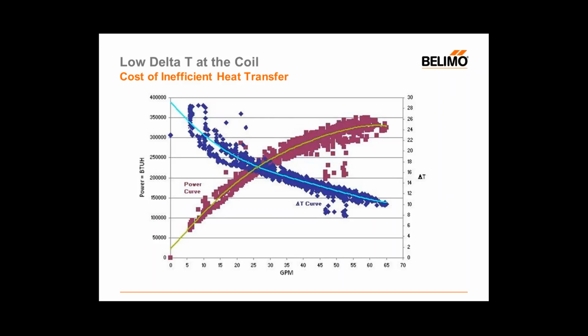Let's talk about what the potential impact of this energy savings would be if we could take a look at it both from the pumping perspective and the plant perspective. So let's start with the pump. And we'll take our clean looking curves and we're just going to pick 2 points on which we could control to relatively the same amount of cooling here. So point 1 on my graph uses about 55 gallons a minute, and it produces about 320 kBTU per hour.